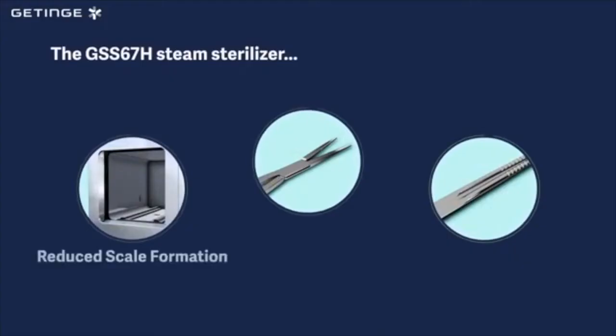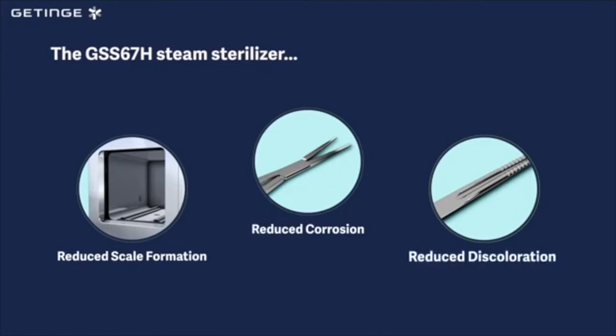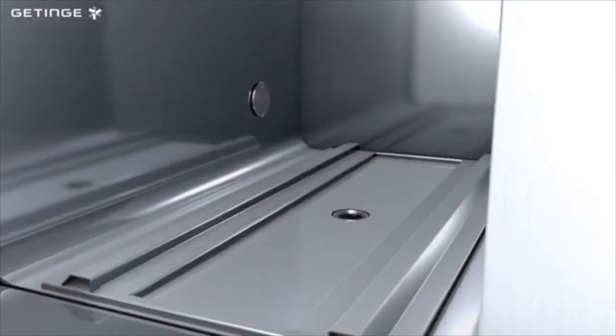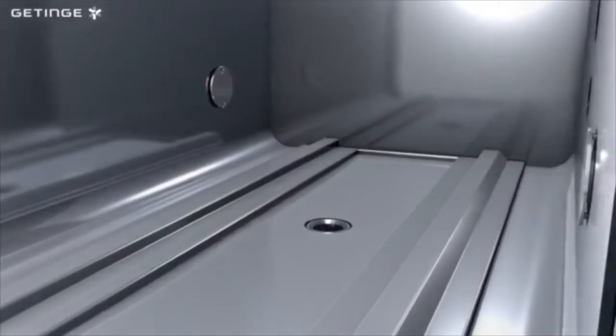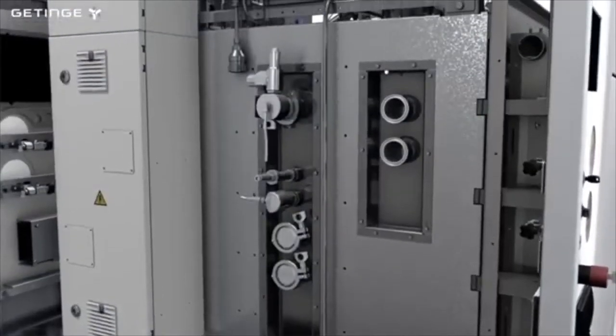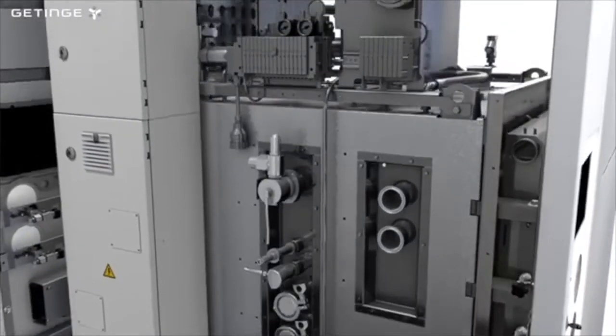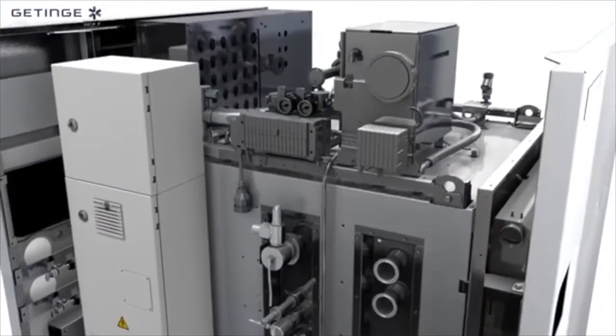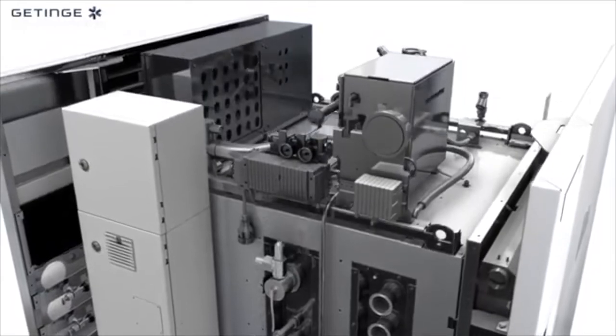An autoclave sterilization agent is steam. Less than 3% humidity produces what's called dry or superheated steam, as this steam increases sterilization time. Superheated steam lowers humidity to about 0%. This transforms the autoclave into a dry heat oven. What takes 3 minutes in an autoclave at 135 degrees Celsius takes 2 hours at 160 degrees Celsius and 30 minutes at 180 degrees Celsius.